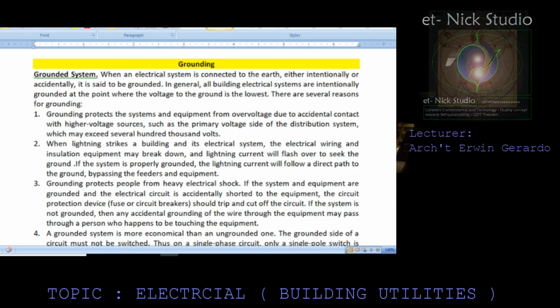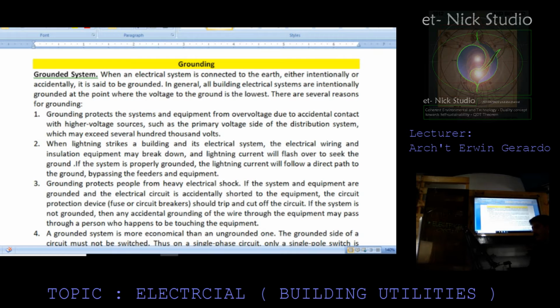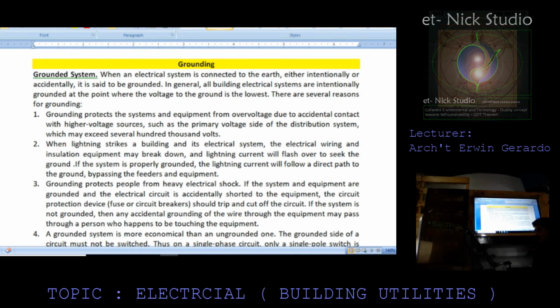Grounding system. When an electrical system is connected to the earth, either intentionally or accidentally, it is said to be grounded. In general, all building electrical systems are intentionally grounded at the point where the voltage to the ground is the lowest. There are several reasons for grounding. One, grounding protects the system and equipment from overvoltage due to accidental contact with a higher voltage source, such as the primary voltage side of the distribution system, which may exceed several hundreds or thousands of volts.